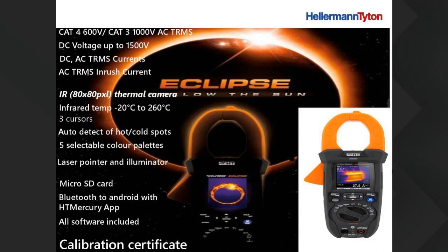Now, the other unique feature of this meter is that it also has a built-in thermal camera. The thermal camera is similar to the Mercury, the previous meter. It's got 80 by 80 pixels. The infrared temperatures the thermal camera can measure are from -20 to 260. It has 3 cursors. It has an auto detect of hot and cold spots that will be visible on the screen. It has 5 selectable color palettes, and it's got a laser pointer and illuminator. All these features of the thermal camera are exactly the same as the previous meter, the Mercury. It's the same family of meters. The only difference is one is a multimeter, one is a clamp meter.